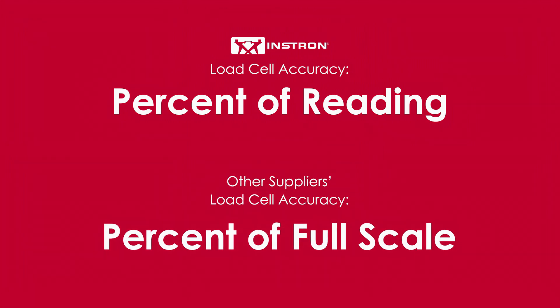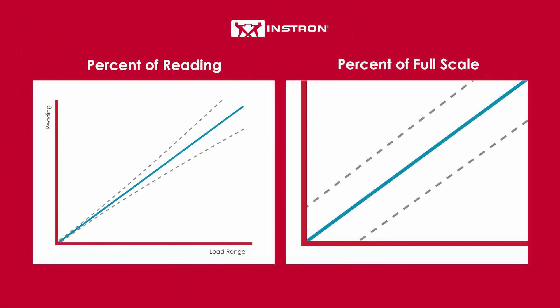Before I go through an example, I want to highlight a few things you should be mindful of. The accuracy of Instron load cells is based on a percent of reading, while the accuracy of some suppliers' load cells is based on a percent of full scale. The important distinction here is that when measuring accuracy as a percent of reading, the error scales with the force reading. Whereas with accuracy as a percent of full scale, the error is constant and becomes much more pronounced with lower readings.